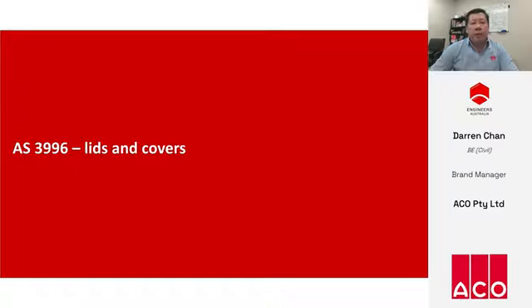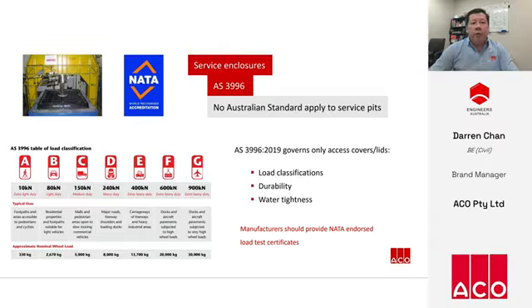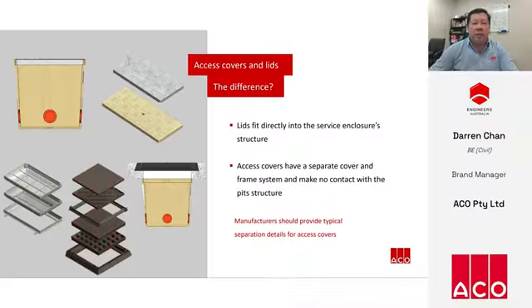Lids and access covers are the physical barriers that come in contact with the external environment. As I mentioned before, there is no Australian standard that applies entirely to service pits. AS 3996 does, however, govern access covers and lids as the bearing elements of direct live loads. This standard was revised in 2019, and compared to the 2006 version, lids and access covers have stricter deflection criteria, and Class D has increased from 210 kilonewtons to 240 kilonewtons for the ultimate load. There are 7 load classes defined by the standard, A to G. Durability and water tightness requirements are also included in AS 3996. Manufacturers should always provide NATA endorsed load test certificates for access covers and lids.